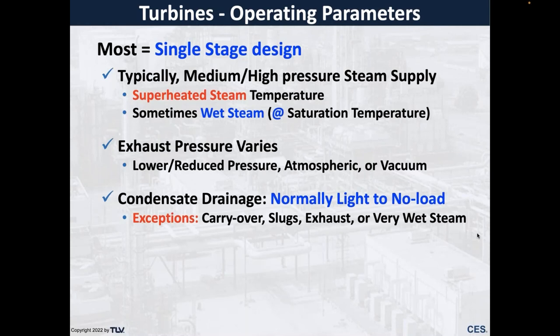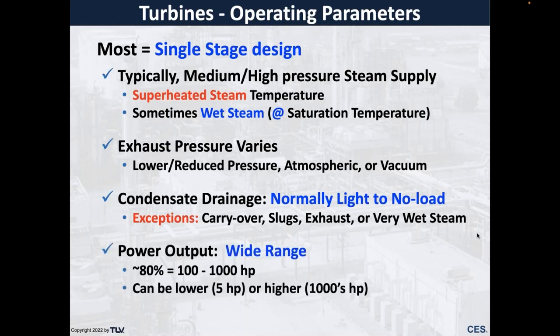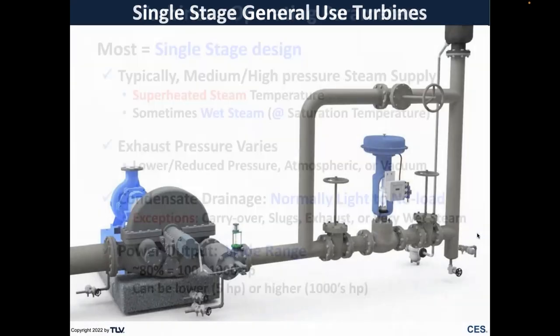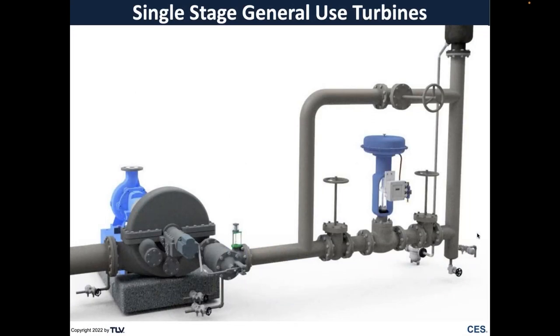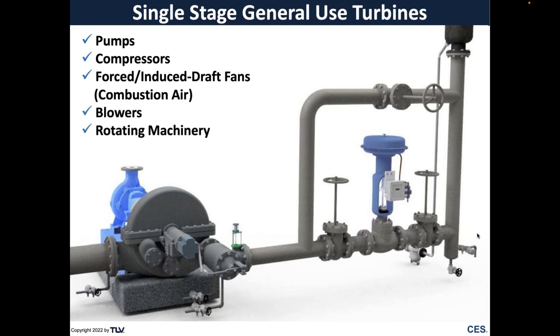Condensate drainage is normally light to no load, but exceptions occur when we have carryover slugs, exhaust load concerns, or very wet steam. It's a wide range of power output, but eighty percent of turbines are relatively small — between a hundred and a thousand horsepower. This is a typical recommended turbine installation used for pumps, compressors, forced air draft, blowers, and rotating machinery.